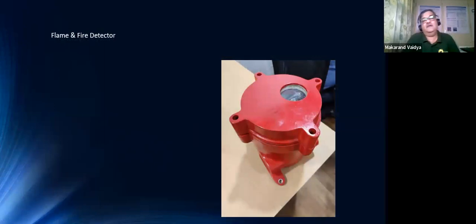With Honeywell, I developed various sensors, and this is the last one, the latest, developed for CNG pumps. In the CNG pumping or compressor room, there are two sensors like this: one at the bearing and second at the control panel, monitoring for any fire or flame occurring. The similar design with different construction and configuration is used in furnaces and boilers. Those were also developed in the past, but I'm not showing those photographs since that is past tense; this is present tense.